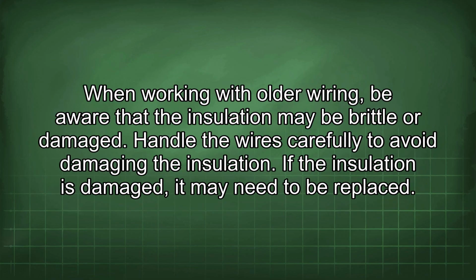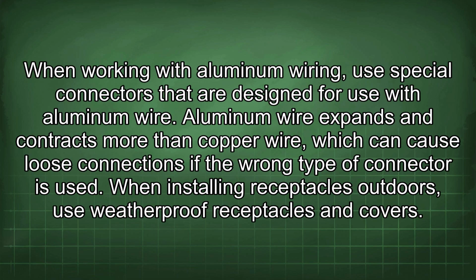When working with older wiring, be aware that the insulation may be brittle or damaged. Handle the wires carefully to avoid damaging the insulation. If the insulation is damaged, it may need to be replaced. When working with aluminum wiring, use special connectors that are designed for use with aluminum wire. Aluminum wire expands and contracts more than copper wire, which can cause loose connections if the wrong type of connector is used. When installing receptacles outdoors, use weatherproof receptacles and covers.